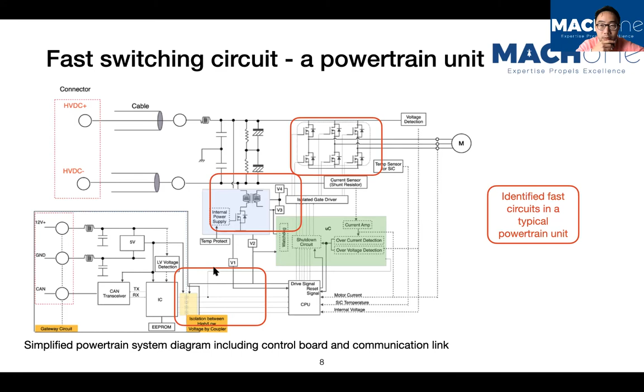On the low voltage power rail, we often have a switching mode power supply that also has a very fast switching switch. For a system like this, you always have to design an isolation circuit between the low voltage part and the high voltage part. We've seen cases where the isolation chip itself has a lot of fast switching events, and these can cause problems. That's also an area people sometimes ignore.